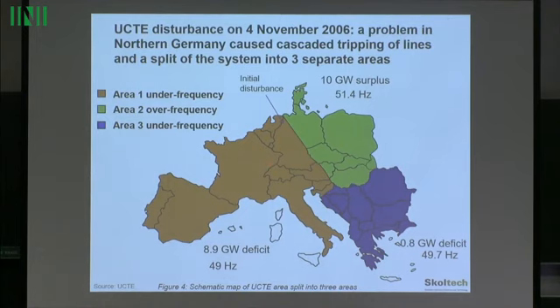But it did separate into areas. That means there was a power flow going from the east to the west. So when you come through those lines, that area had a surplus, so power frequency went up to 51.4. Here there was a huge deficit because they lost all the supplies, an 8.9 gigawatt deficit, so the frequency dropped to 49 hertz. In the southeast area there were just little deficits of frequency, no problems, but over here there were huge problems.